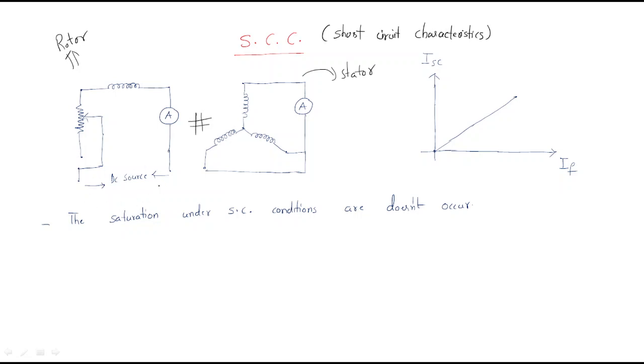The rotor is excited with a DC source — this is the rotor field. The stator is a three-phase circuit that is shorted. All three terminals are shorted through an ammeter. The relation between the field current and the short circuit current gives the short circuit characteristics.